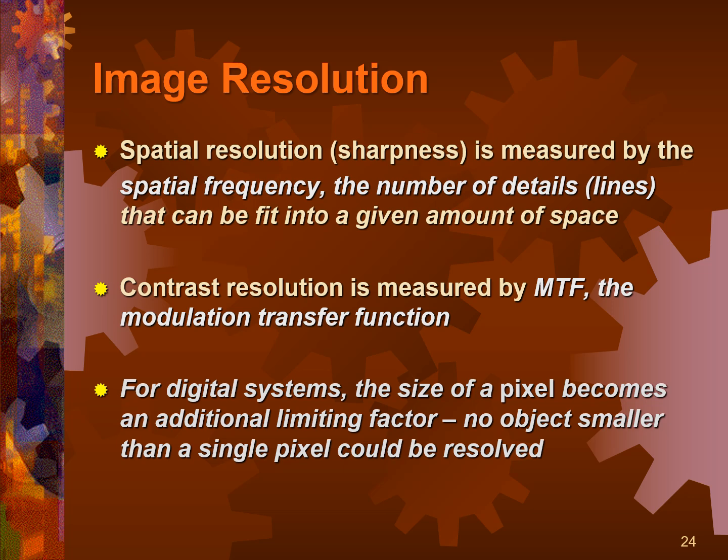If it's smaller than the width of your pixels in your imaging system, the X-ray machine is not going to be able to demonstrate that. It's just going to demonstrate a gray blur. In other words, it loses the ability to transfer an actual frequency, that is, an object frequency, and display it as an image frequency. In other words, it's a modulation or frequency transfer function. Okay?